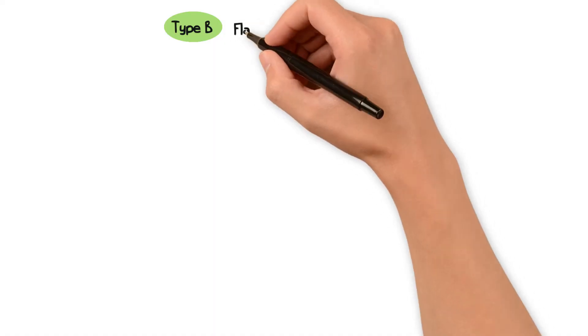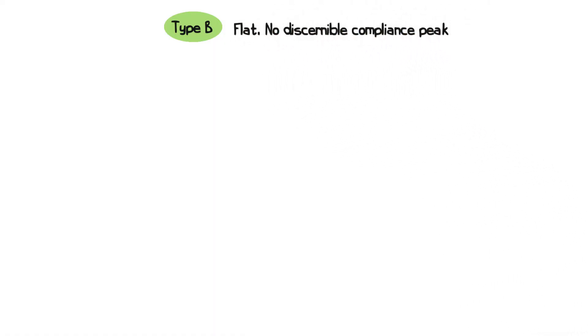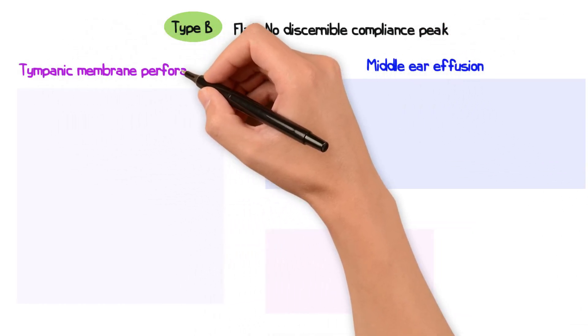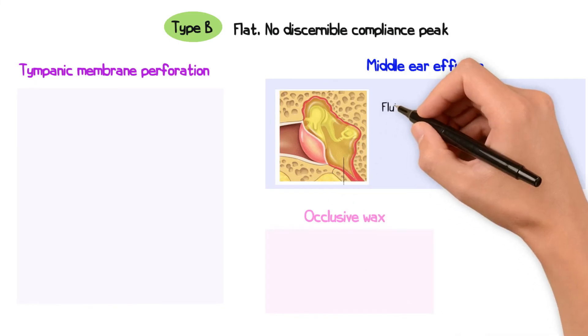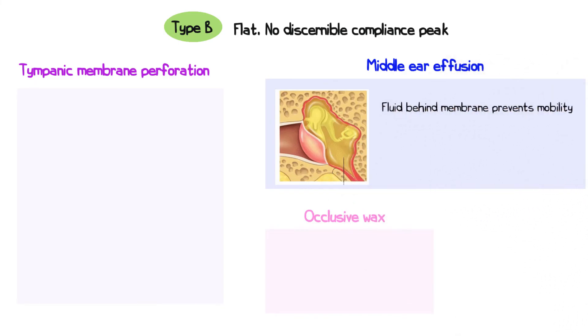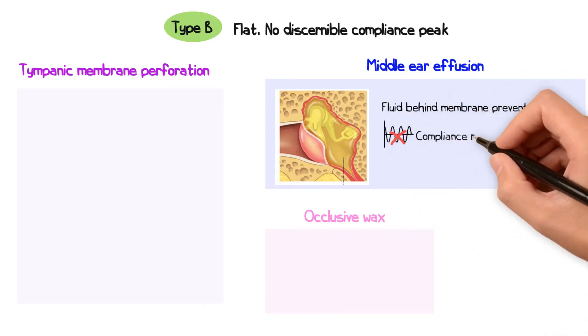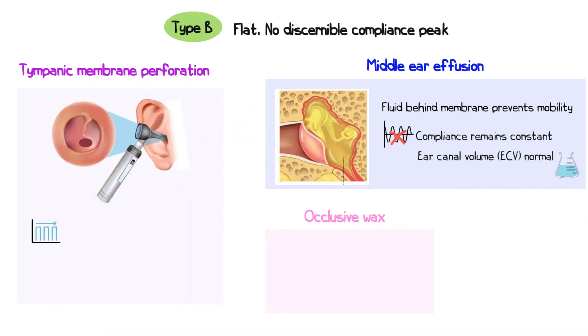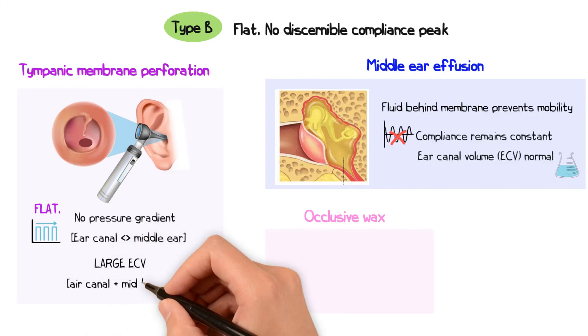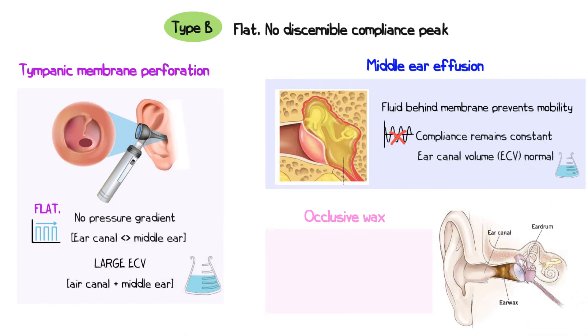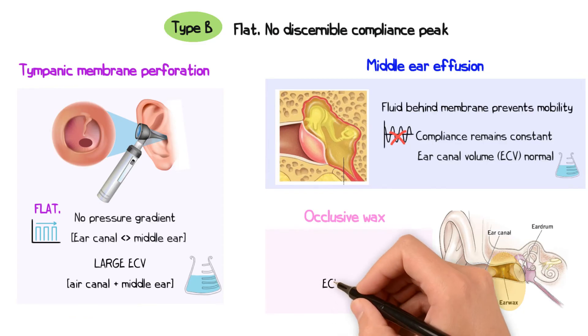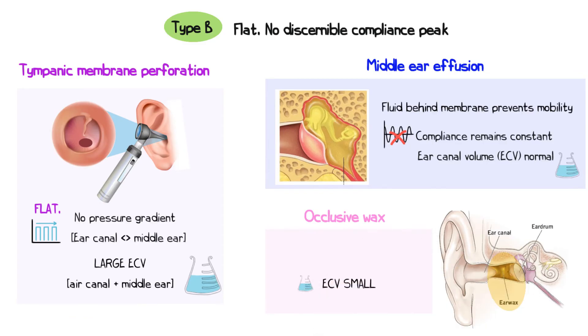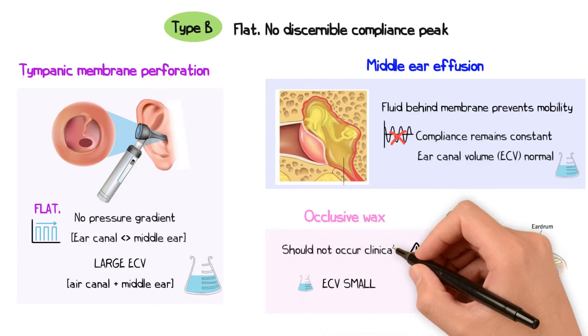A type B trace is a flat tympanogram indicating no discernible peak in compliance. This could be due to middle ear effusion, tympanic membrane perforation, or potentially occlusive wax. If fluid is present behind the tympanic membrane, its movement is restricted, resulting in no variation in compliance with pressure changes, and the ear canal volume in these cases is usually normal. When the tympanic membrane is perforated, the air pump is unable to create a pressure gradient, resulting in a flat trace, and the ear canal volume will be larger than normal. If a plug of wax is occluding the external auditory canal, a flat trace will also occur but the ECV will be abnormally small. Typically, wax is removed prior to tympanometry, so this situation should not occur in clinical practice.